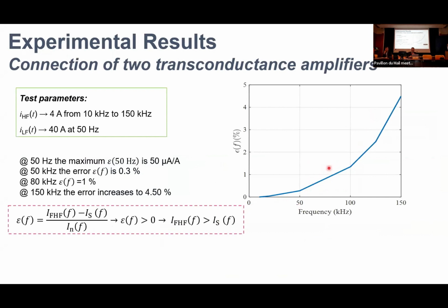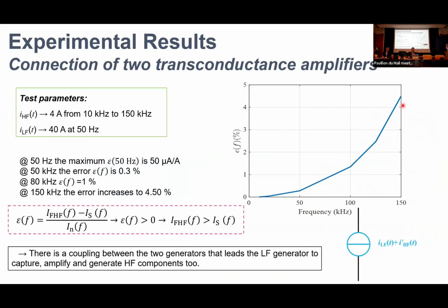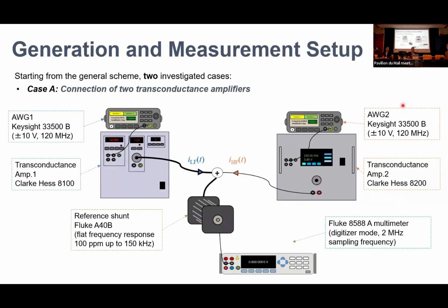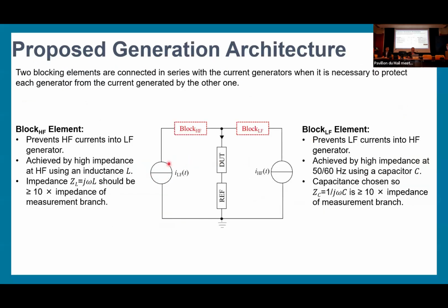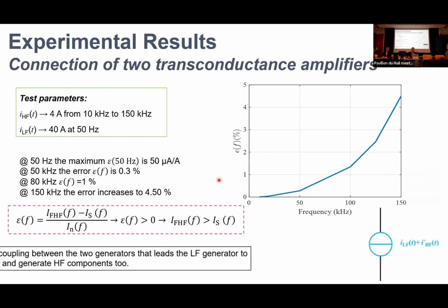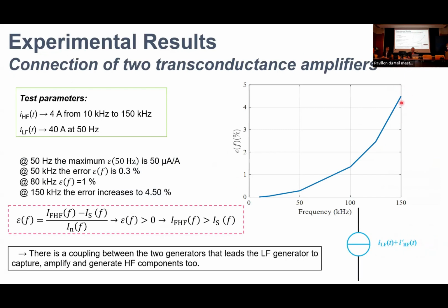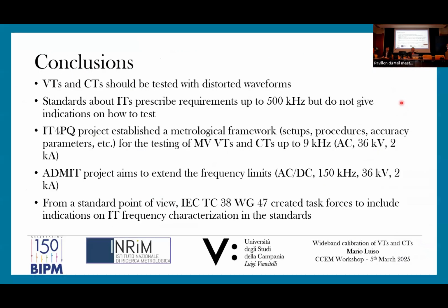This is a graph of the error between the desired current at high frequency and the measured current. At high frequency, 150 kilohertz, the error is quite high. So without blocking elements, the error is quite high because the generators interact with each other and a portion of the high frequency current flows in the low frequency generator, is amplified and comes back to the load. And this is why we have such a high error at 150 kilohertz. So attention should be paid in the design of the blocking element.